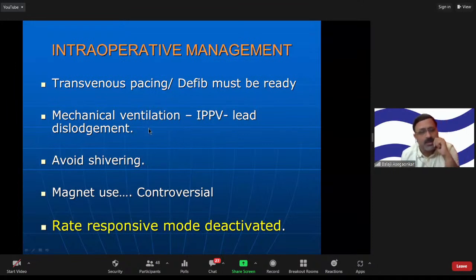Now, magnet use. Previously, it was said that whenever such a patient comes in emergency with a rate sensitive pacemaker, you put a magnet and naturally it will put that pacemaker on an asynchronous mode. But now this is controversial. Nowadays, pacemakers are coming with a lot of sophistication, and just using a magnet will not revert them to an asynchronous mode. So nowadays, magnet use is very much restricted.